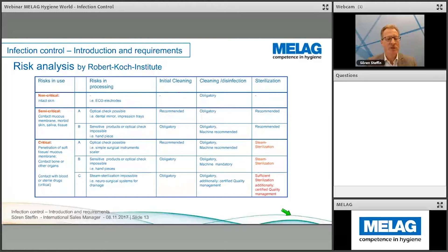Depending on the setup of semi-critical instruments, a disinfection is recommended — we have to perform a disinfection; sterilization would be nice and bring the instrument to a safe level, but it is not demanded or required. But for all invasive instruments — the critical instruments — we have to perform the entire cycle: proper pre-cleaning, disinfection, and sterilization. Here, steam sterilization is the state of the art, because that procedure has a lot of advantages. We can refer to other webinars for more detail on this subject.